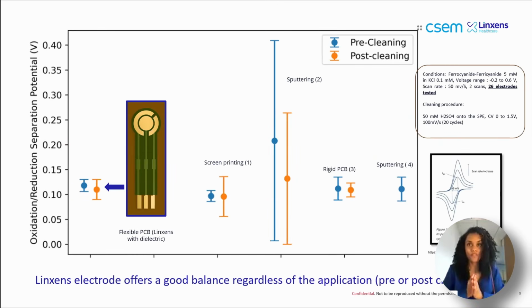So we continue this analysis, this electrode performance evaluation. We try to see if the cleaning impacts the quality of the performance of our electrodes. So we study the oxido-reduction peak separation potential. And just for your information, in general, a good reversible system presents an oxido-reduction peak separation potential of around 59 millivolts. In our case, with and without cleaning, we have an oxido-reduction peak separation potential of around 100 millivolts. That is quite good for a disposable gold electrode. And as you can see, if you compare our performance with the other technologies available on the market, our reproducibility and the performance that we can present is quite good.